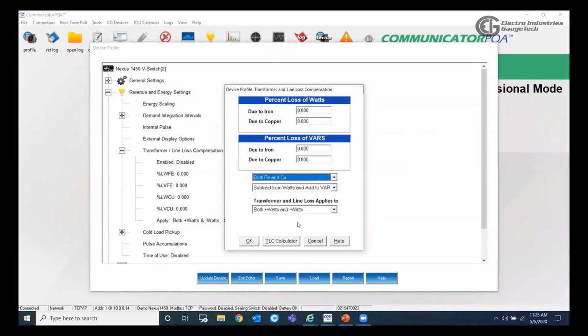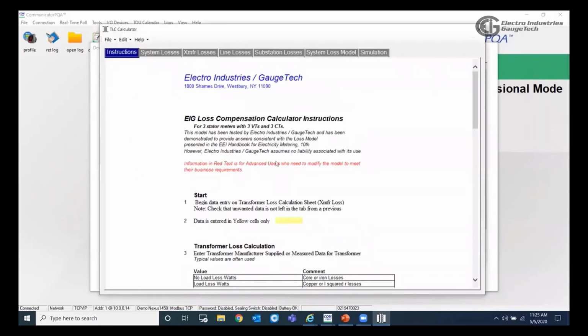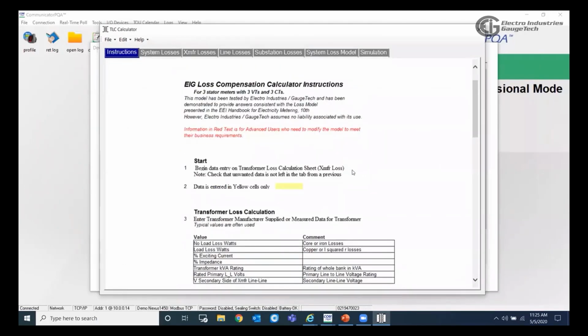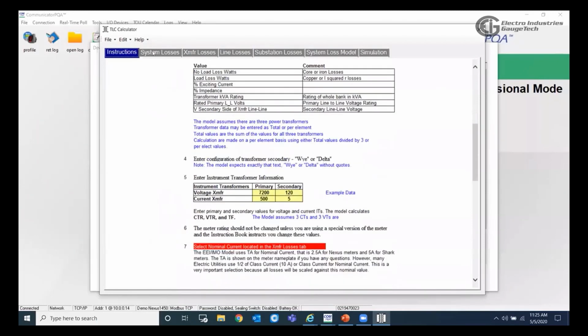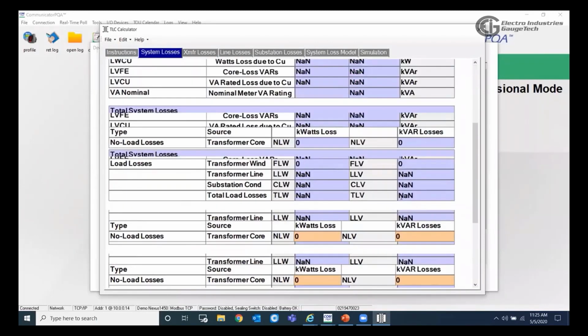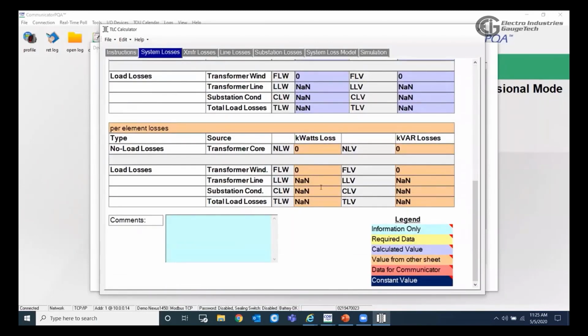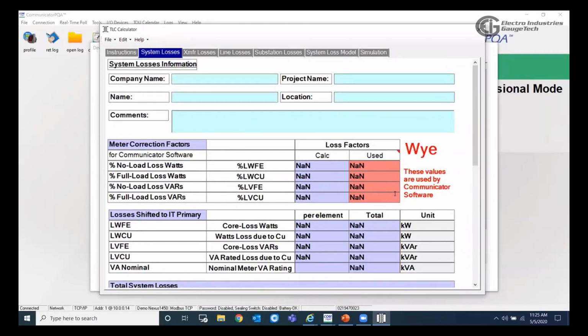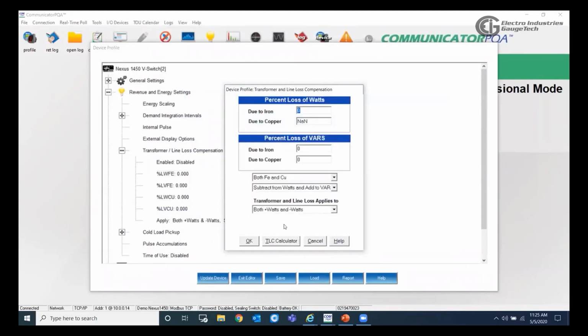And once it's enabled, you have to go to the TLC calculator. To do this, you have to get that information for the transformer and the line, and that should be given by the data sheets of that transformer. So you have to input these values, and after entering all the data, you will get the values you have to use at this one here.